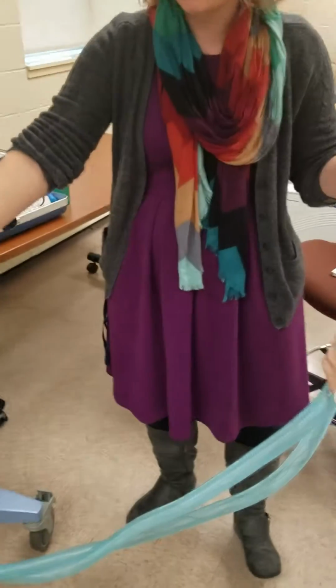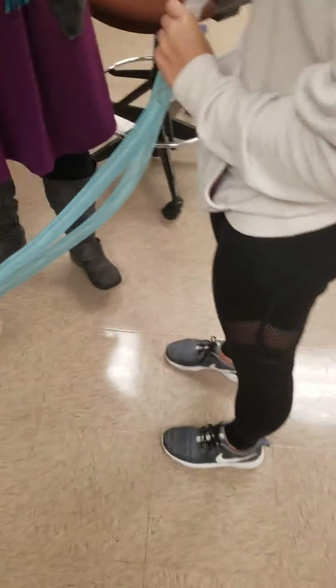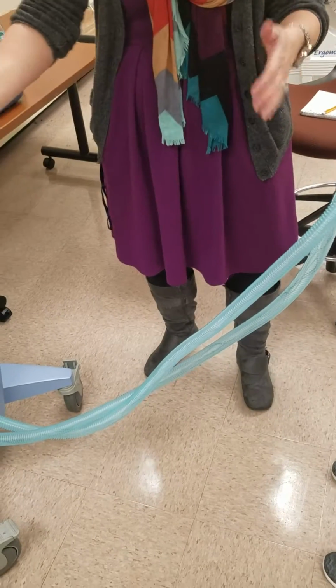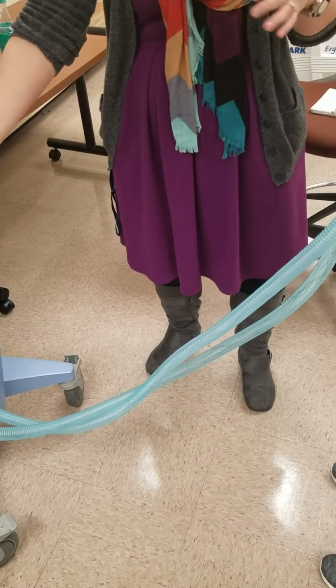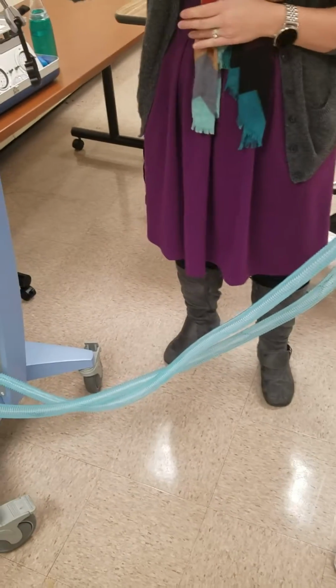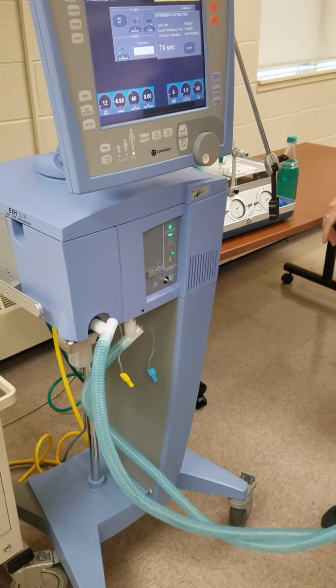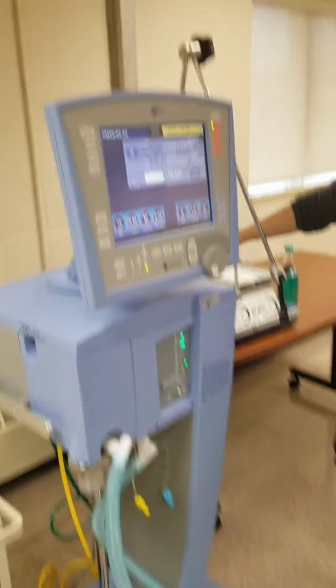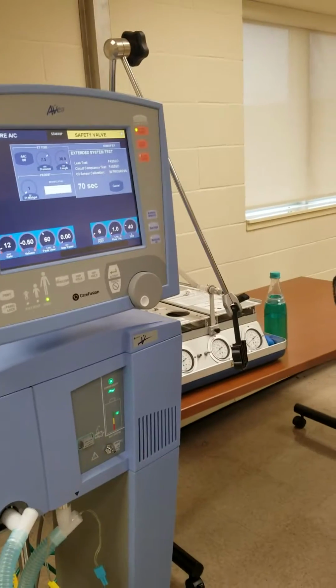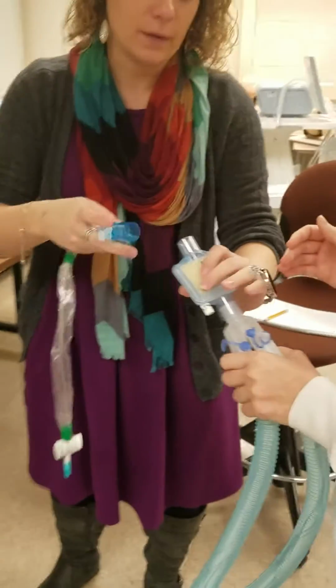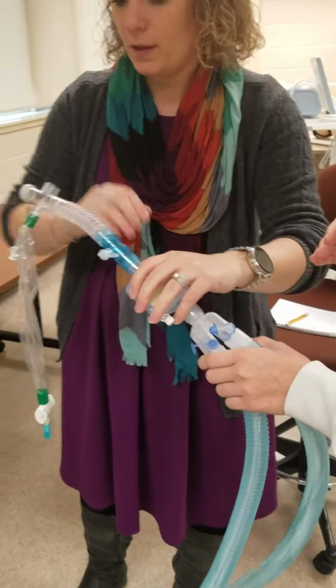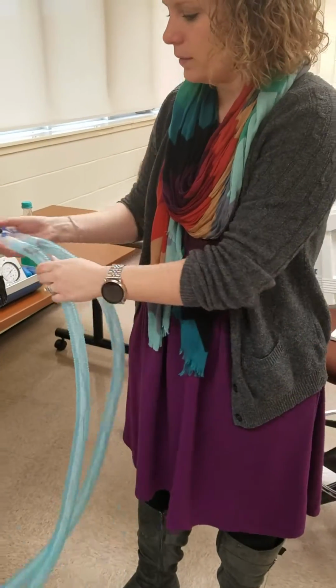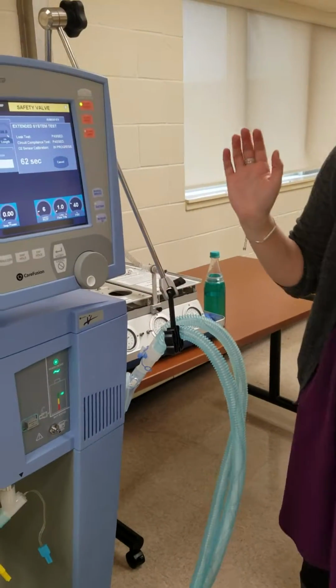The first two pieces are a leak test and a compliance test. It's filling the circuit up with air, and then it's going to check to make sure there's no leaks anywhere, and it's going to do some calculations to figure out what the compliance of the circuit itself is before we hook it up to the patient. They both pass, so now you can let go. Next is the O2 sensor calibration, and it'll fail because our O2 sensor is expired, and they're really expensive, so we're not replacing it. We'll go ahead and just move this over here.